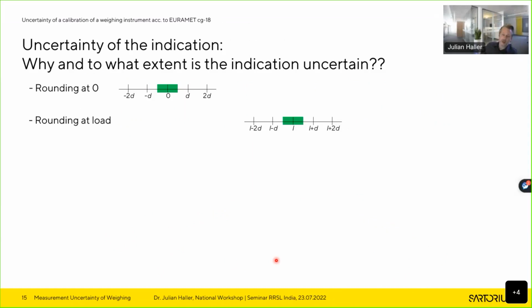Actually, you have one or two contributions that are always there if you have digital measuring instruments. If your balance shows 0 in the beginning, you just know that the true internal value is between minus half a digit and plus half a digit. So you do not know what the internal true indication is, because you're limited to the digitalization of the instrument. That is an uncertainty contribution that we have to consider. The same applies if you read the final value: if you read 100 gram, you just know the indicated value is between 100 minus half a digit and 100 plus half a digit. And that is then also taken into account.